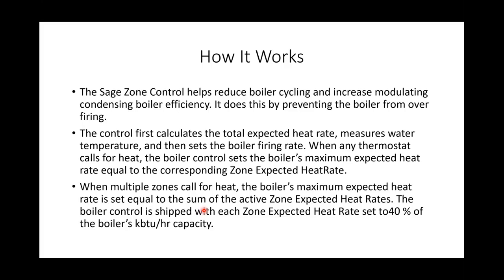So basically what this does, it allows the boiler to modulate within a window. Okay, zone 1 is 40,000 BTUs. I have a Raptor 105. It's going to modulate from 10,500 BTUs to 40,000 BTUs, which will be the window that zone 1 modulates in. Zone 2 has 60,000 BTUs, so now it's 10,500 to 60,000 BTUs. It'll modulate in those windows.